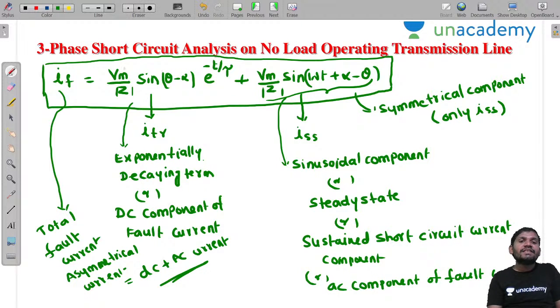Okay, this is the calculation of fault current if any short circuit fault occurs on a transmission line. So it is very important, sir, that you concentrate. What you get is Vm by Z into sine of theta minus alpha, where theta is the impedance angle, or power factor angle, because of R and L, the line parameters of the transmission line. In e power minus t by tau, tau is L by R, the time constant.